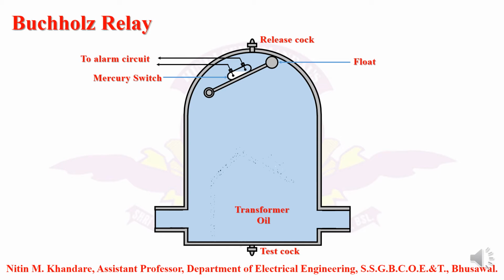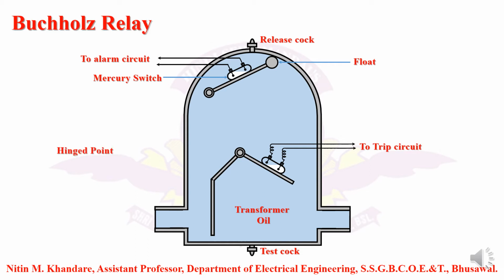Then the second system is called as the hinge flap system. Again one mercury switch is connected with that, and the output of the second mercury switch is connected with the trip circuit. The top system is connected for the incipient fault, and the bottom system, that is the flap system, is used for protecting against the rapid acting faults. So this is the hinge point. The next component is nothing but the flap which is connected in between the flow of the transformer oil. Then from the left hand side we will connect the transformer tank, whereas the right hand side end will be connected with the conservator tank. So this is the construction of the Buchholz relay.